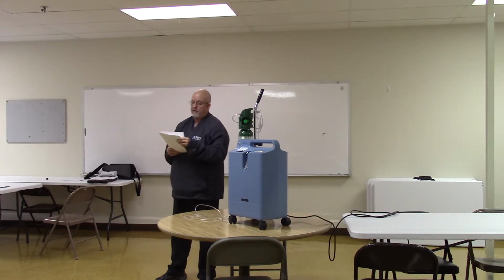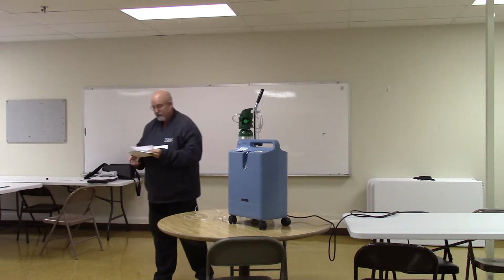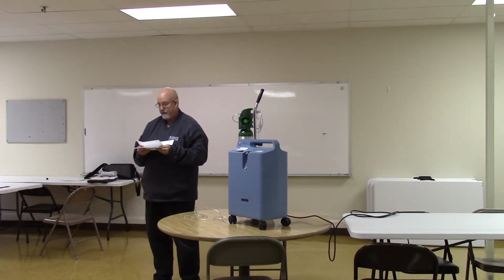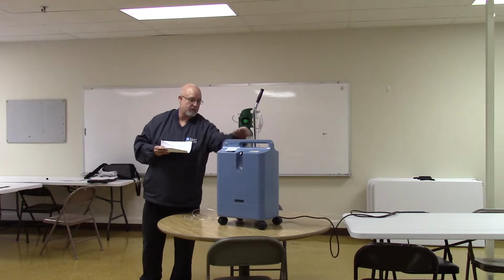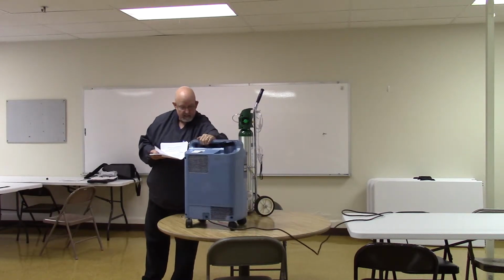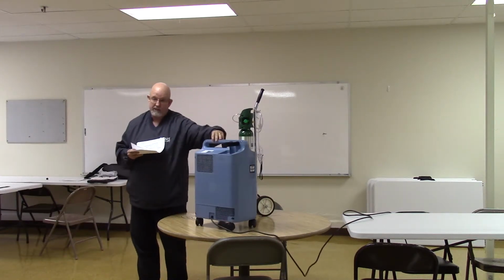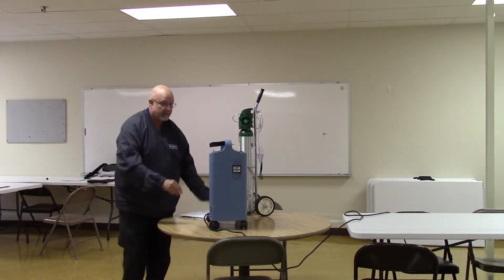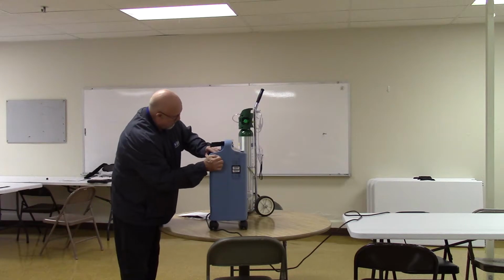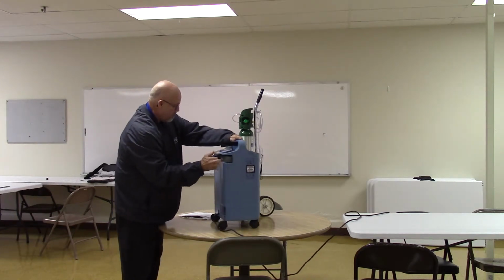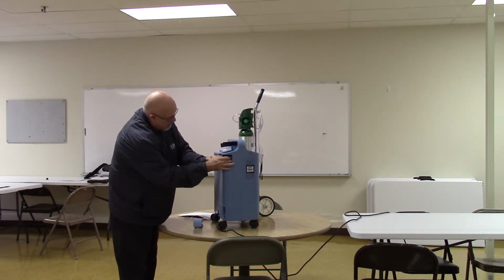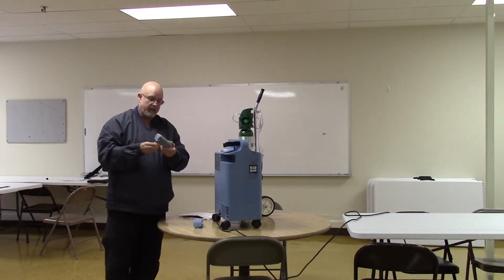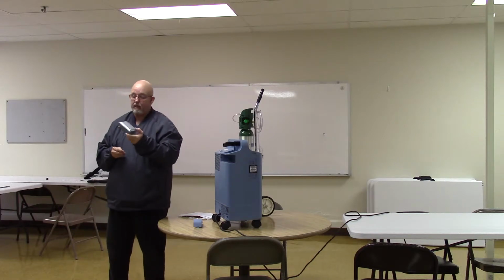These days it's the most common oxygen source. Concentrators and their filters should be maintained for optimal function. This actual machine does not have a filter that you guys can change. Yeah, there is one in here. That needs to be changed yearly, and then somebody from my company will come by and do that.